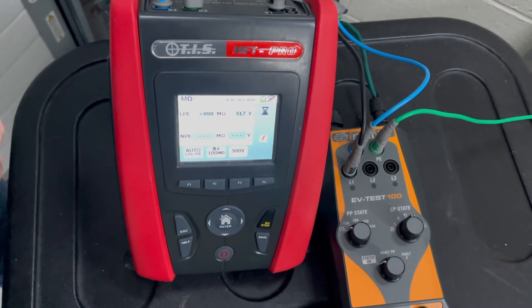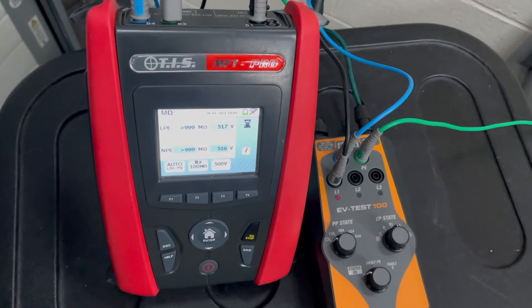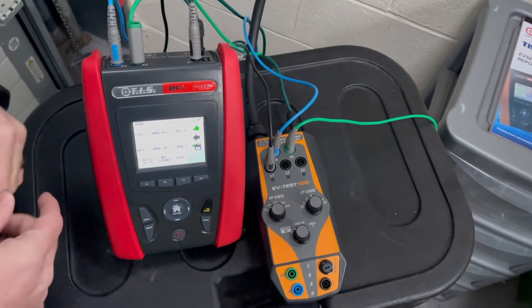The LPE reading is good — greater than 999 — and the NPE reading is the same, having delivered 516 volts. So the insulation test is good. That's the insulation test complete.